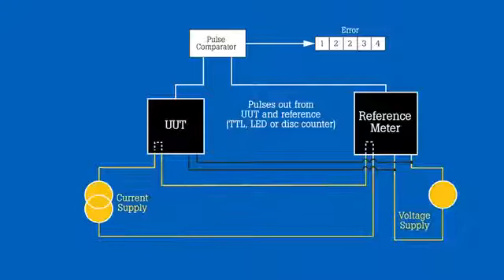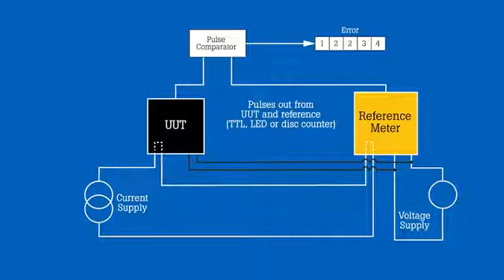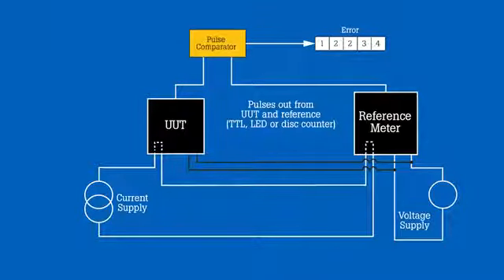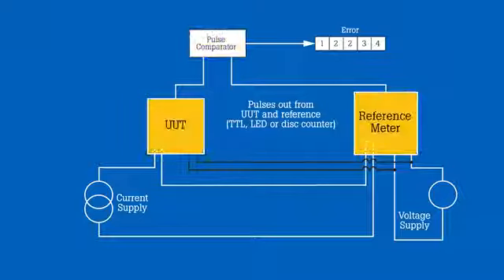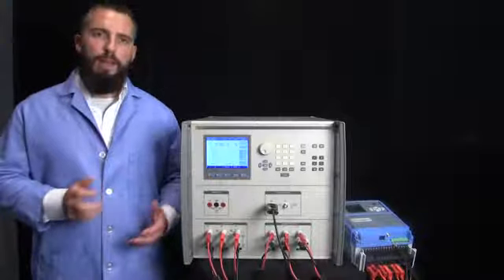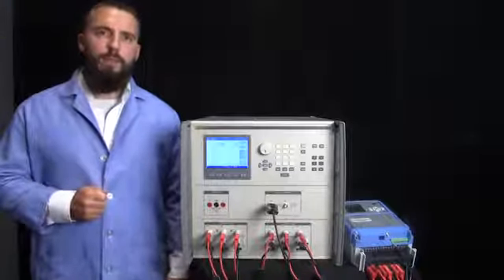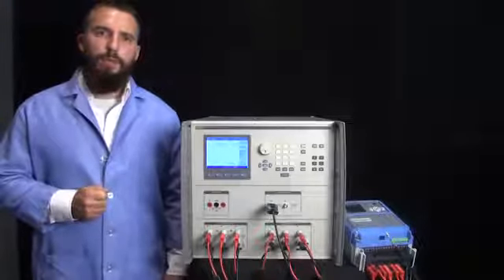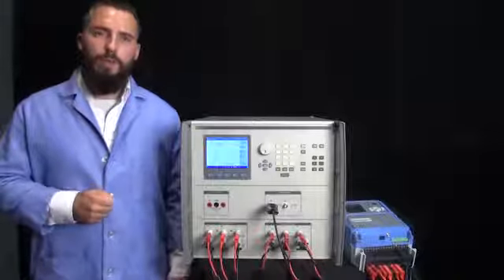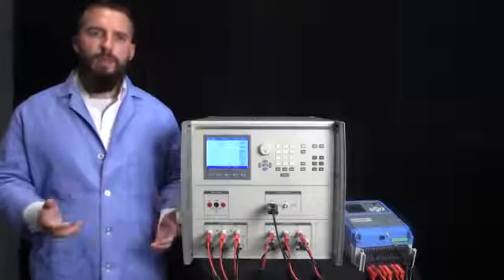1. A power supply that can provide 3 phases of voltage and current. 2. A 3-phase reference energy meter. And 3. A device for counting pulses both from the reference meter and the UUT, which then compares the two counts. As you can imagine, this is a lot of work to make sure that each piece of equipment is connected and communicating properly. How can this process be simplified, you may ask?